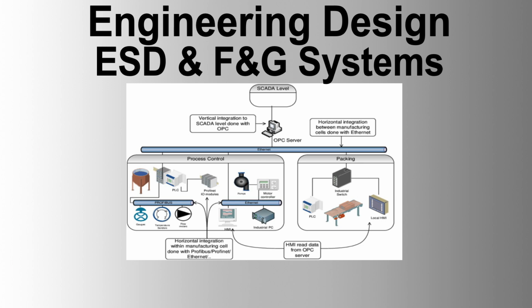Design information. Given by purchaser. The following documents will be given to the vendor to implement the system: process flow diagrams, PFDs, piping and instrument diagrams, P&IDs, ESD and FGS cause and effect matrix, control system block diagram, SIL study report, ESD and F&G IO list, local equipment room, LER, layout, fire and gas layout, DCS function block diagram, existing functional design specification.